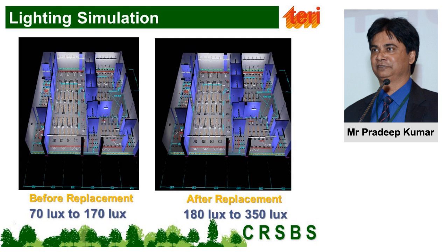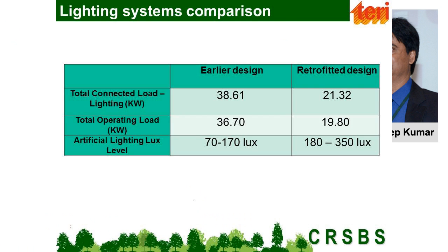So there is a significant increment as far as the lighting levels, or the quantity of lighting, is concerned. This was done beforehand, before the retrofit starts. The second thing: in the earlier design, the total load was 38.61, and after retrofitting it is estimated at 21.32 kilowatt.